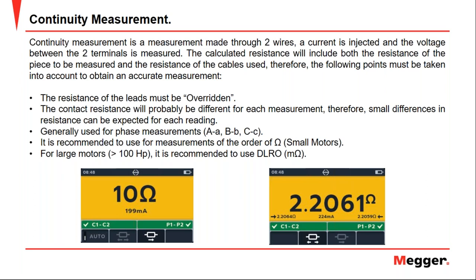The first thing that we have to do is override the resistance of the lead. This is the first thing to do. And we have to take into account that the contact resistance will probably be different for each measurement. Therefore, a small difference in the resistance can be expected for each reading. So this procedure is recommended when the resistance value to be measured is in the order of ohms, a case that usually occurs in small electric motors.